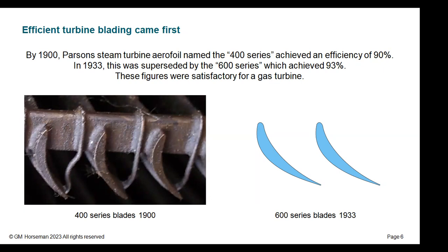In 1933, the blading on the right was introduced. This was named the 600 series blade, and this raised the efficiency level to 93%, which for those days was quite a good performance level. And either of those blades would be perfectly suitable for a gas turbine. It's the 600 series blade on the right-hand side that was actually used in the Parsons gas turbines. So that was easy.